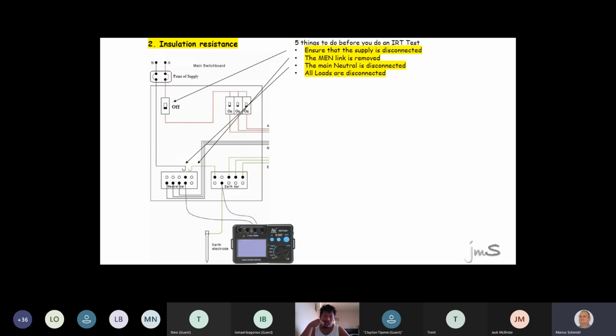Right? All right, guys, and very, very important, all the switches must be on. So you must make sure that the light switches are on, otherwise you do not check the switch wires. You must make sure that your stoves are on because they form part of the installation. You must go to the heater towel rail and switch it on because otherwise you never check the switch wire. Is it true that the switch wire goes from the switch to the appliance? If you don't switch them on, you don't check that wire.